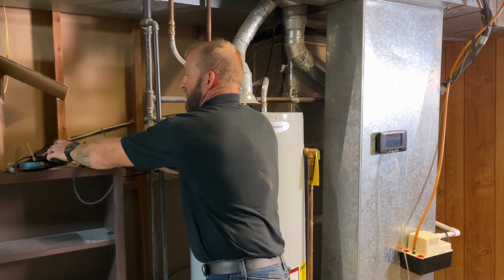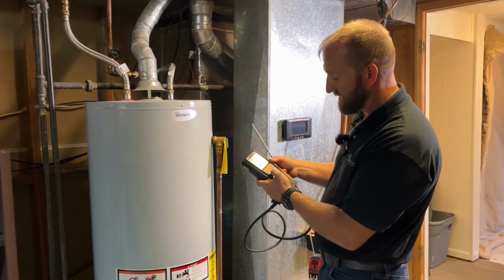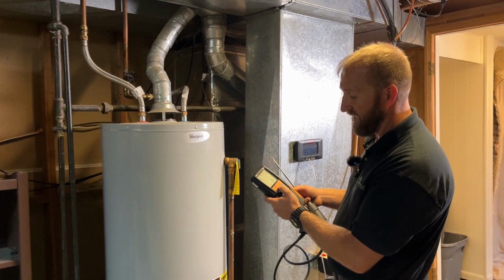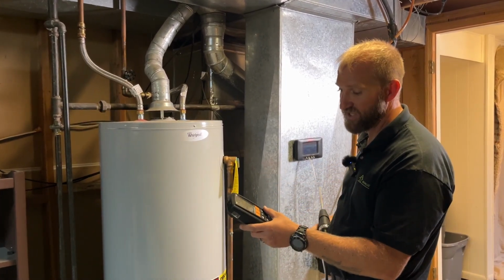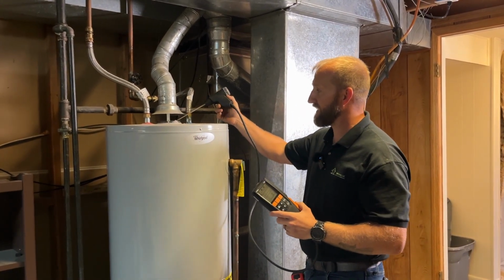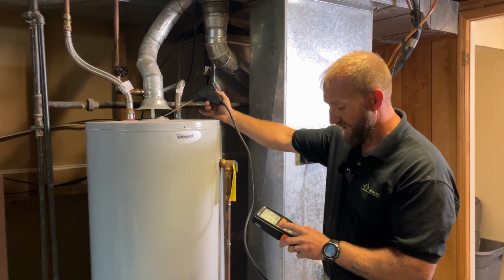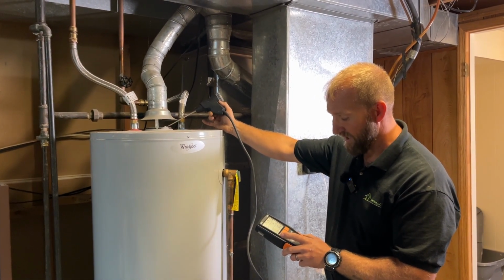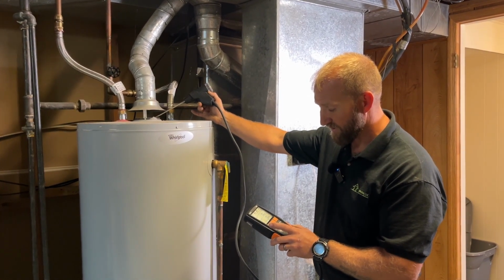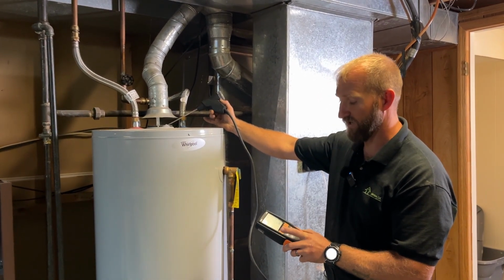Then at the 5-minute mark, we're going to take our combustion gas analyzer. We're still going to be on the flue gases, but on this one, we're going to scroll up and we're going to be reading undiluted flue gas, where it says UCO, undiluted flue gas. We're going to stick it down into the throat of the unit and let it stabilize. Looks like we're bouncing between 1 and 0, so that's really good. So we're just going to call it 1. So we're going to mark that down.